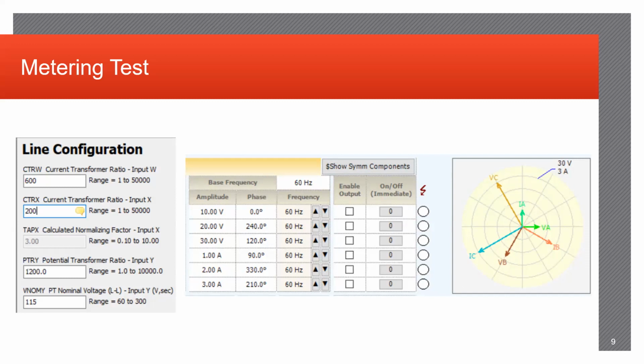different values for each phase is so that when you do look in the relay in real time while you're injecting these values, you can correctly identify that each phase correlates properly. Because if you put 10 on all 3 phases of your voltages, you're going to look in that relay and it's going to be all the same value. So you're not really verifying that each phase correctly replicates what's being read on the relay. Same goes for the currents as well.